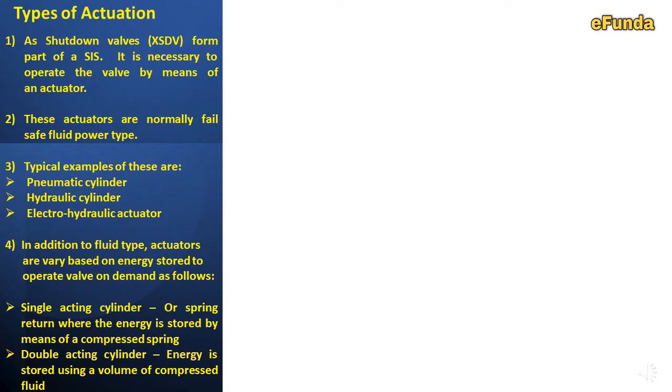electro-hydraulic actuator. In addition to the fluid type, actuators vary based on energy stored to operate the valve on demand as follows: single acting cylinder or spring return, where the energy is stored by means of a compressed spring. Double acting cylinder, where energy is stored using a volume of compressed fluid.